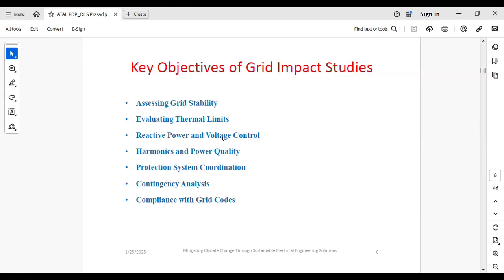That means to analyze the performance of the plant. So we are taking a reference point, that is our point of interconnection. There we are evaluating whether the plant is maintaining the power factor of 0.95 leading or lagging or not. So we have to verify that by conducting reactive power analysis.